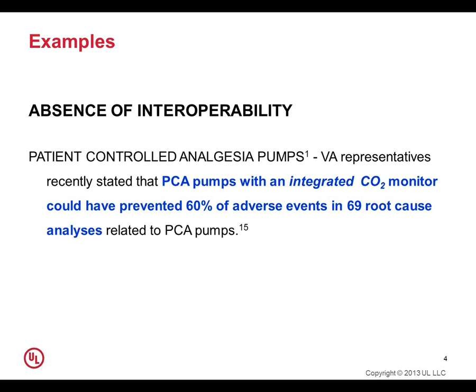In addition to alarming, an integrated monitor would have halted further opioid delivery by deactivating the pump, thus addressing the risk of opioid overdose. So the absence of interoperability actually did contribute to possible adverse events in the field. In contrast, when devices are connected together, that is, when they take advantage of interoperability, and risk mitigation for those hazards which could result from the connectivity not working as anticipated are not effectively addressed, the possibility for adverse events up to and including severe life and health risks can occur.